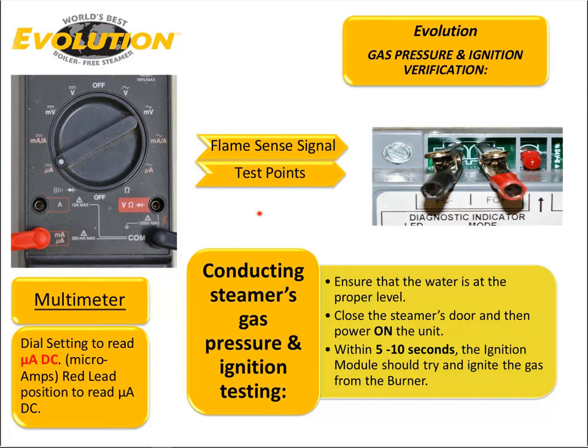On the Evolution steamer, you would check this flame sense at the ignition module itself. We've got a small picture here. There are 2 pins. We do recommend using alligator clips to connect to them because they are very small, and holding a multimeter probe to those is difficult while you're still trying to watch your own multimeter. With your multimeter connected and set to DC microamps, this is the symbol you should see on your multimeter.